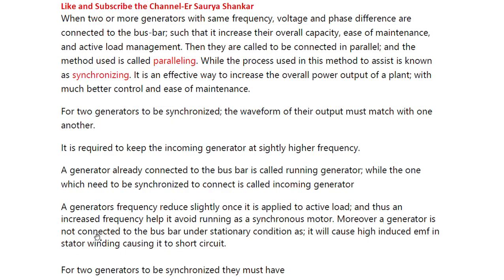An increased frequency helps the incoming generator avoid running as a synchronous motor. In the absence of this, it will run as a synchronous motor, which is the reverse of a generator. Moreover, a generator is not connected to the bus bar under stationary condition, as it will cause high induced EMF in the stator winding, causing it to short circuit.